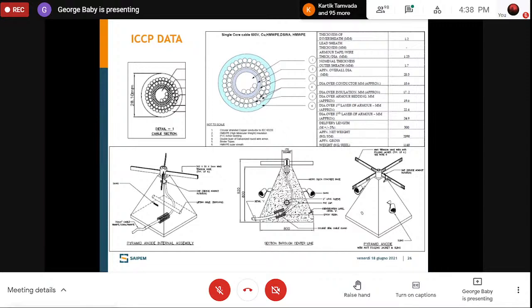And the third kind of cable which we use in the offshore oil and gas industry is the ICCP cable, impressed current cathodic protection cable. These are meant for the protection of offshore steel structures which are installed in the middle of the sea. An anode will be deployed on the seabed, and the cable will connect from this anode to the platform. The anode will protect the offshore platform, which is the cathode.